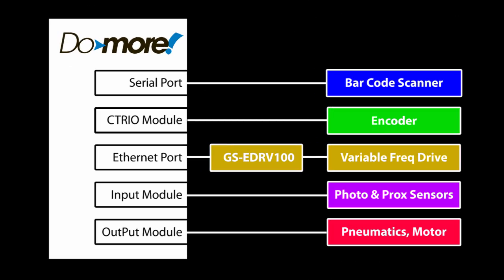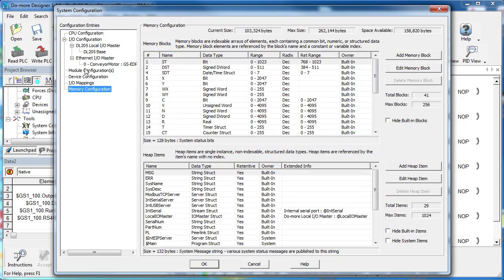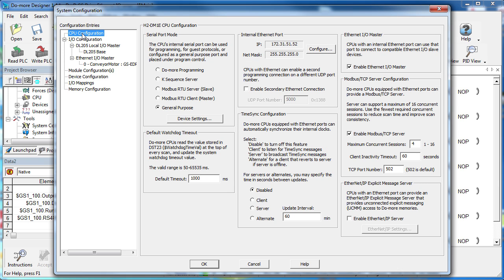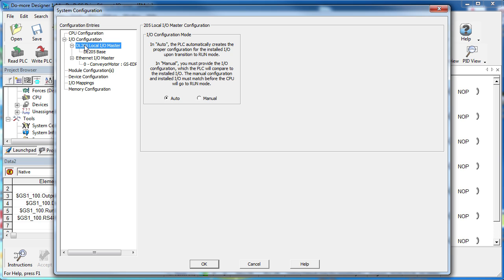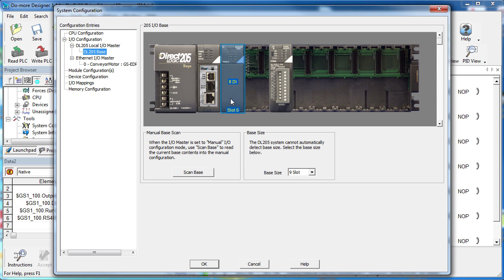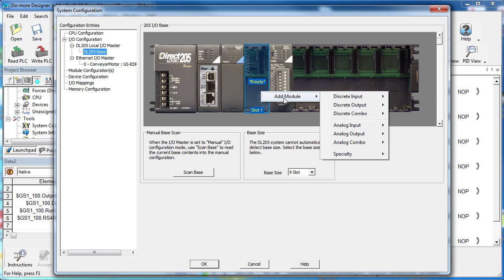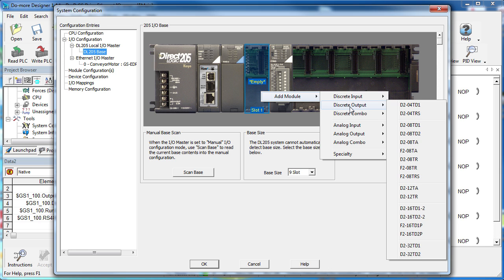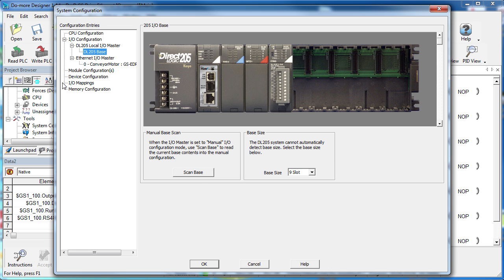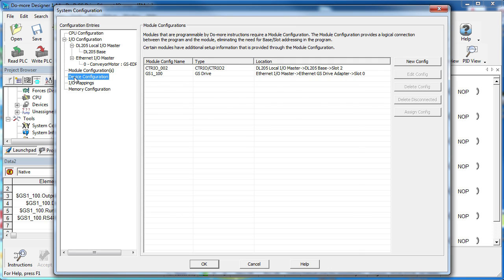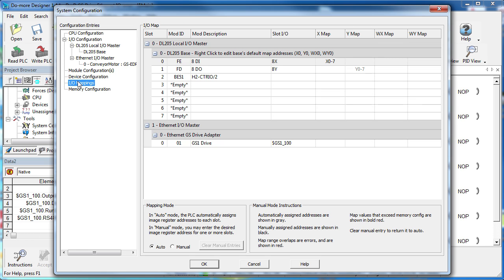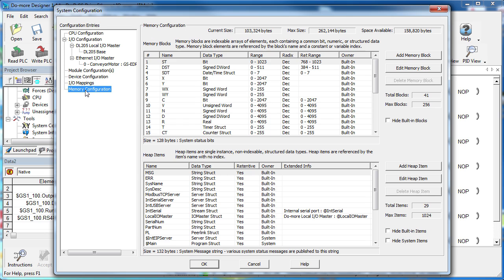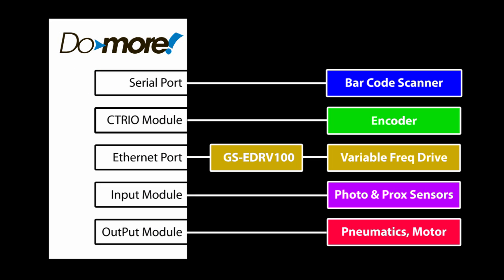Setting up the input and output modules is easy. We'll start back at the top of the configuration list, just like everything else. These don't impact the CPU, so there's nothing to do here. In the I/O configuration, we can see that the Do-more automatically identified the input module and mapped it to memory for us simply because we plugged it in. You can add modules manually by selecting this radio button and then down here right click on the slot to choose your module. I don't have an output module yet, so I'll drop one in manually in this slot. There's no module configuration for these guys and there's no device configuration for discrete I/O modules. The I/O master takes care of all of that for us. I/O mappings. You'll want to leave that on automatic most of the time. But if you want to reserve memory for a future module, you can always switch over to manual and force the I/O mapping to be whatever you want. Finally, there is no memory configuration for the I/O, so we're done configuring all of the devices we need for our project.